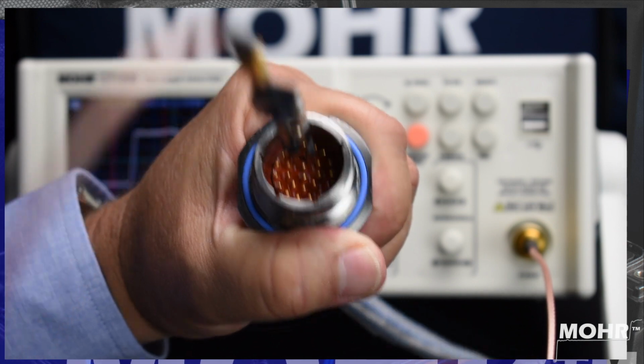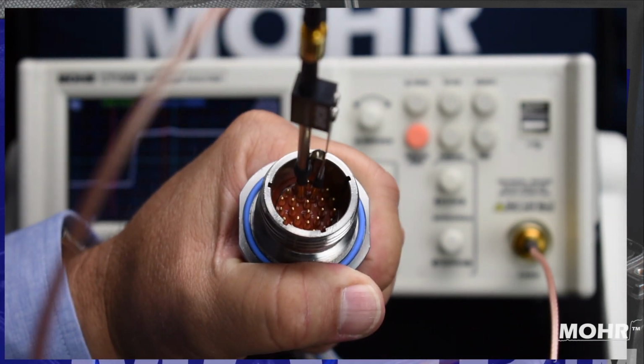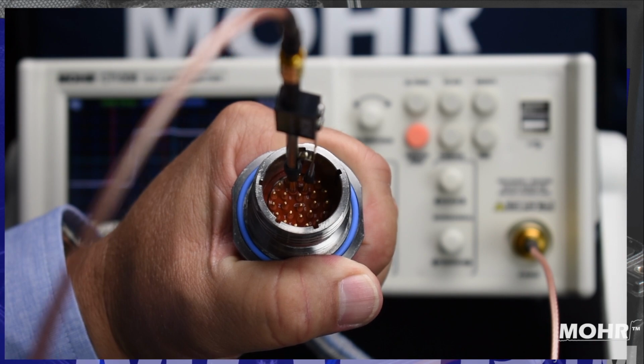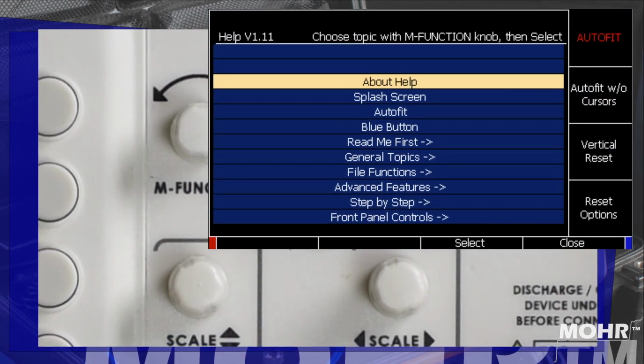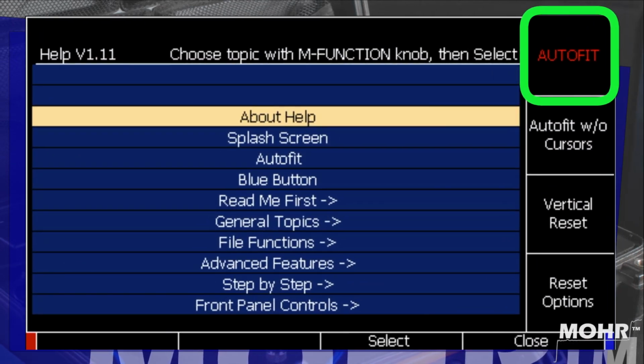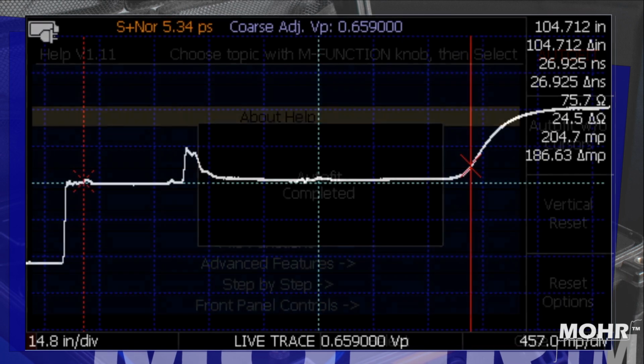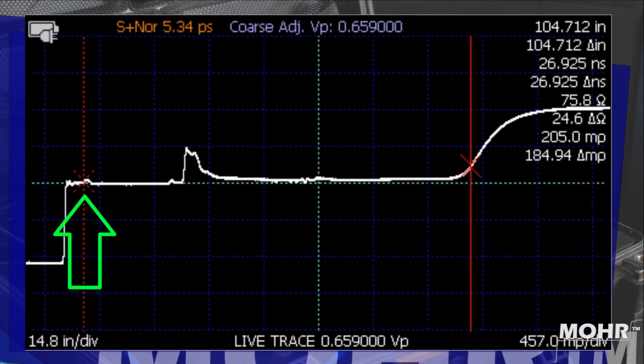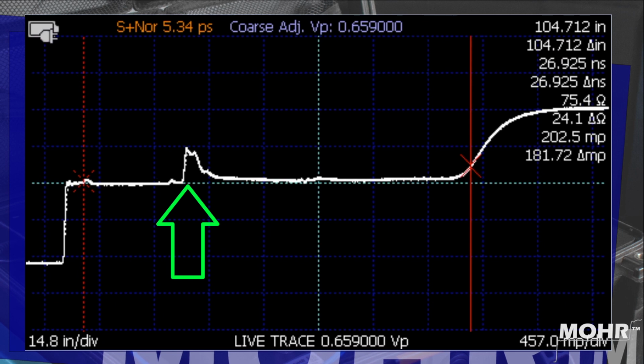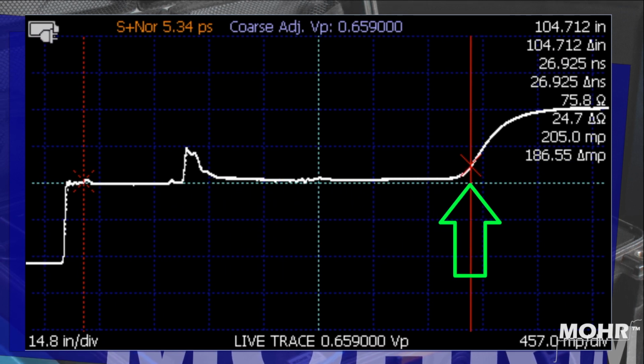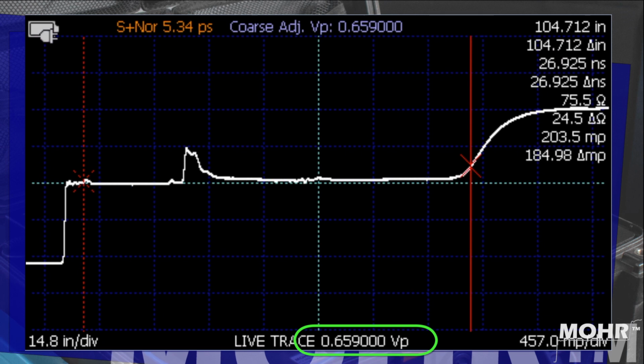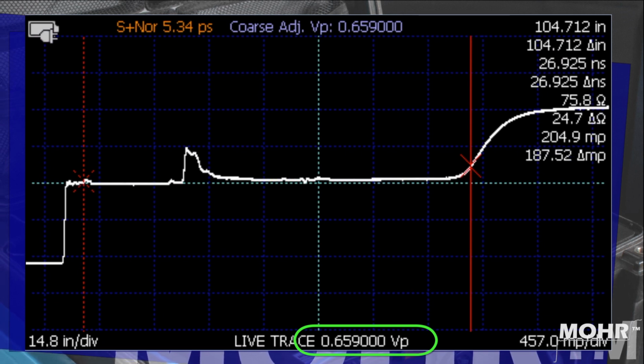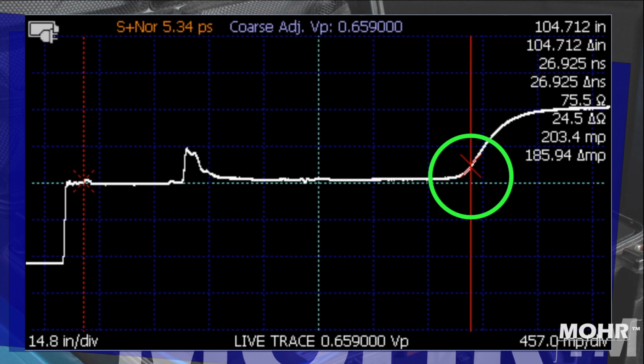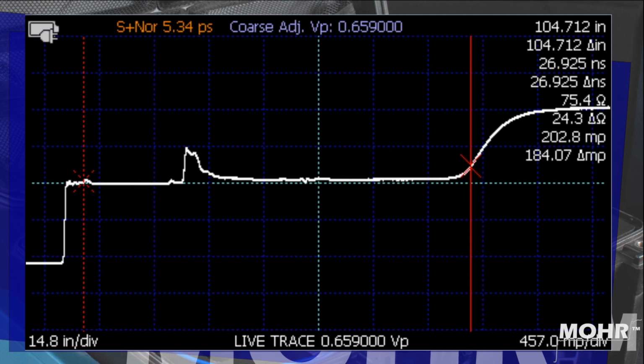I've connected to the S and T pins as our known good pair, and we'll compare this trace to some other examples. Pressing the orange AutoFit Help button brings up the built-in Help menu and gives you the option to select AutoFit from the Quick menu. The AutoFit feature will show the entire trace from where it leaves the CT100B, through the connection we made with the probe, and all the way to the end of the cable. To give us an accurate length, I've set the VP for this cable at 0.659. And AutoFit places the second cursor at the end of the cable, as you can see here, where the impedance climbs sharply.